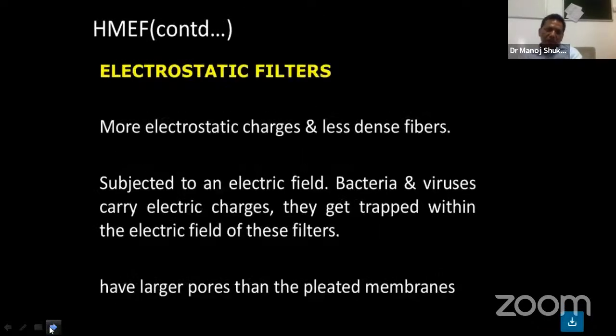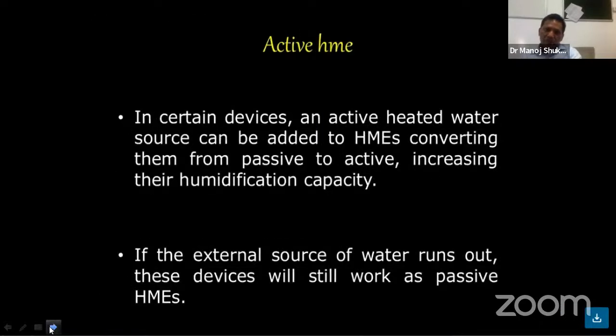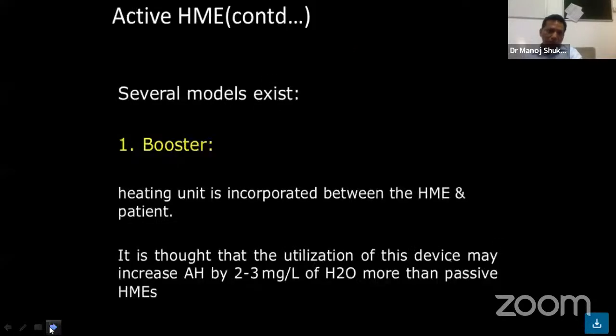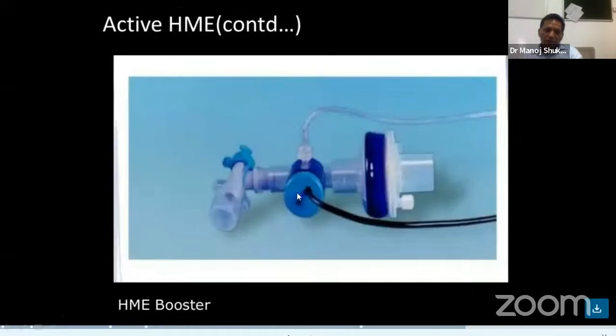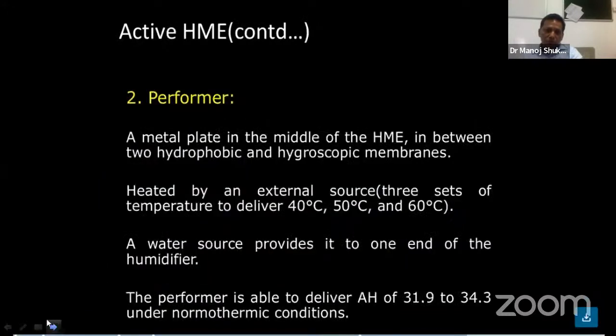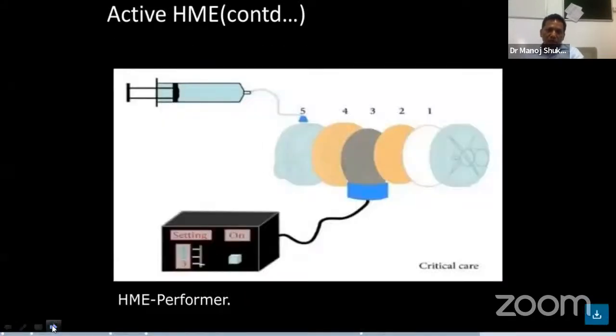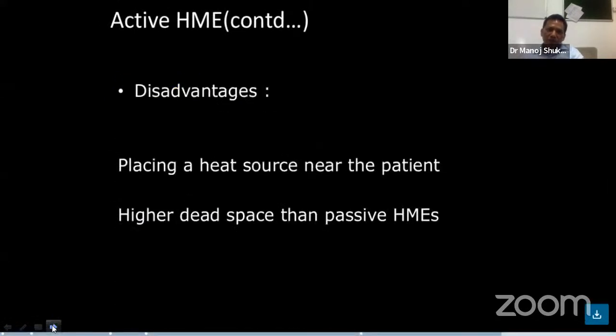These are various kinds of heated electrostatic filters. Regarding the active HME: an active heated water source can be added to an HME, converting them from passive to active, increasing their humidification capacity. If the external source of water runs out, these devices will still function as a passive HME. This is a very modern device — like a booster — called an HME booster. The disadvantage is placing a heat source near the patient and it has higher dead space than passive HME.